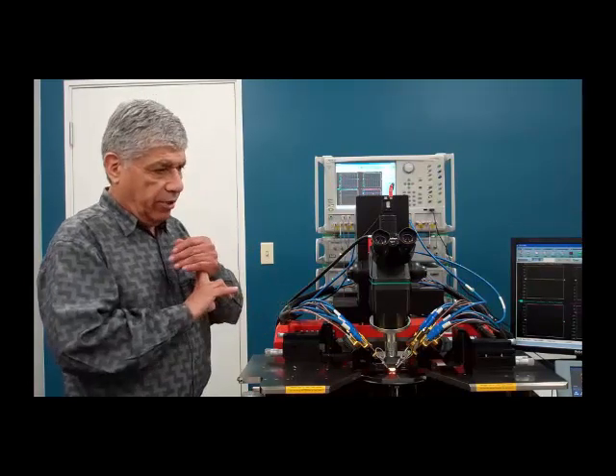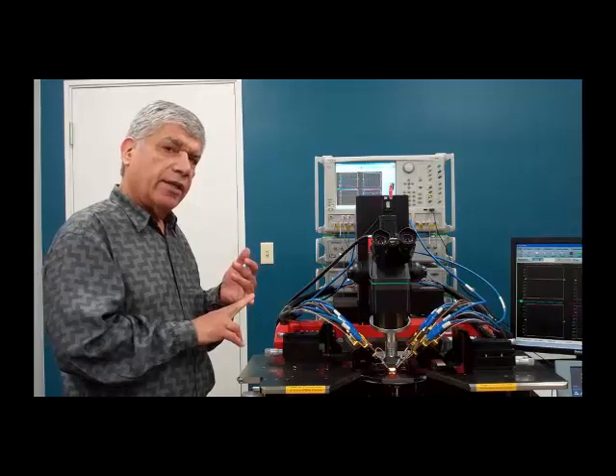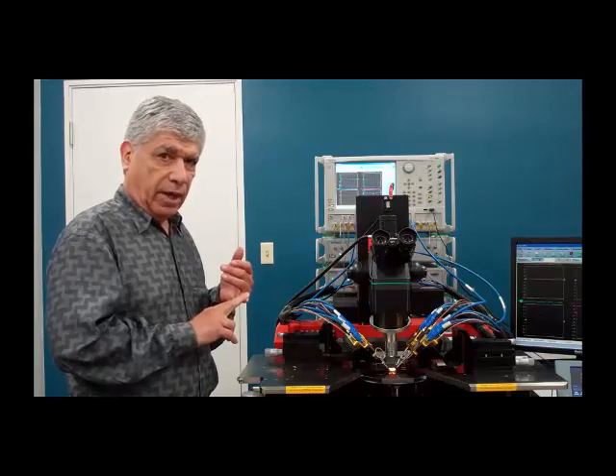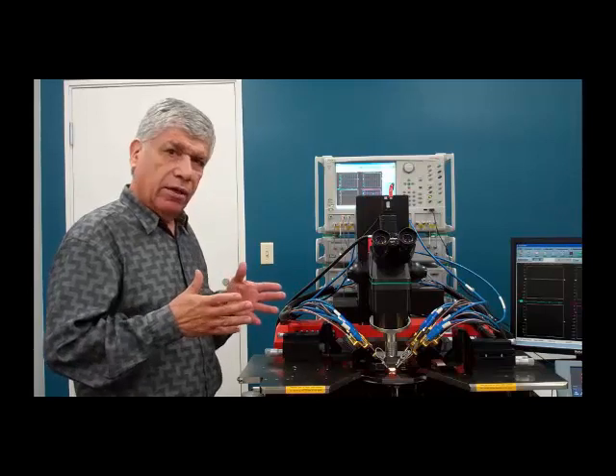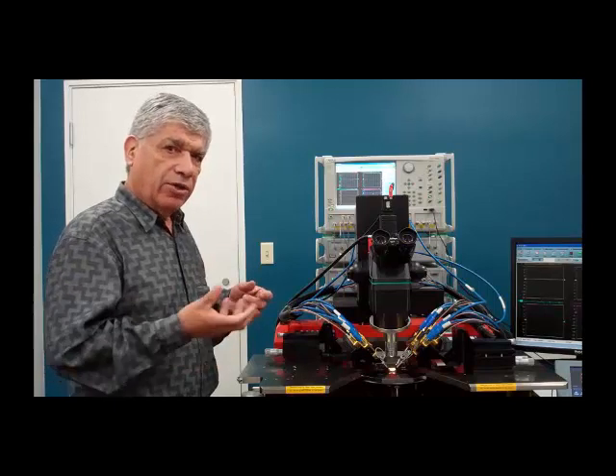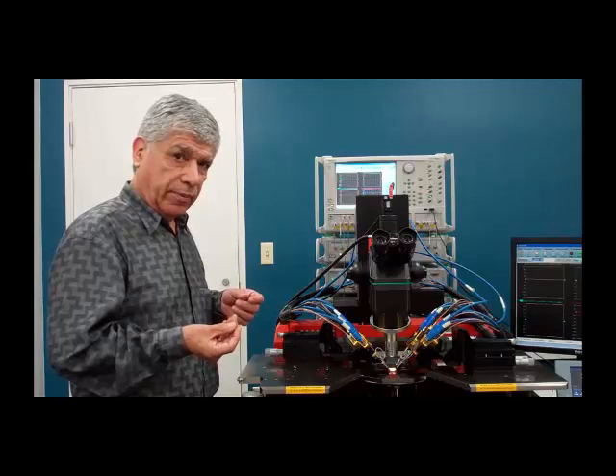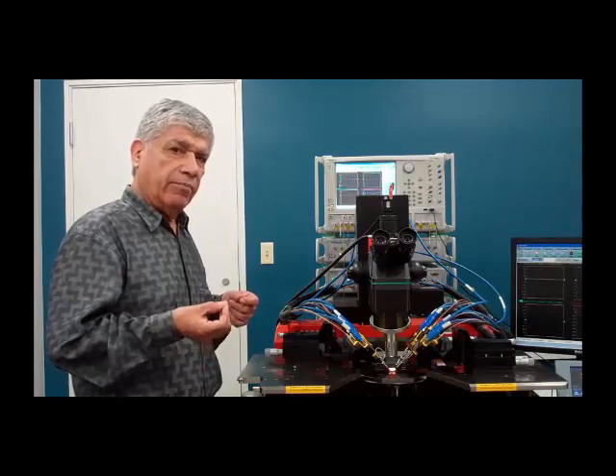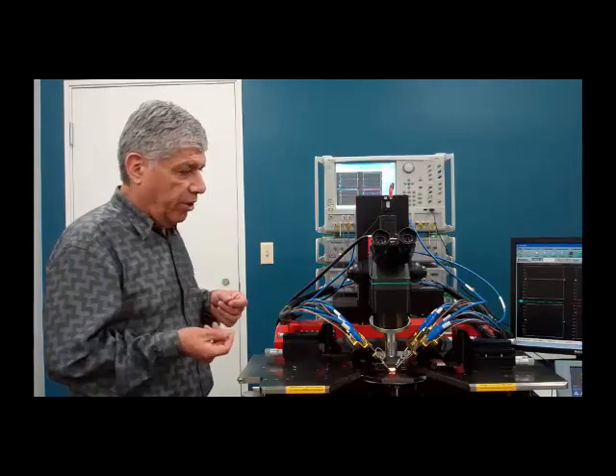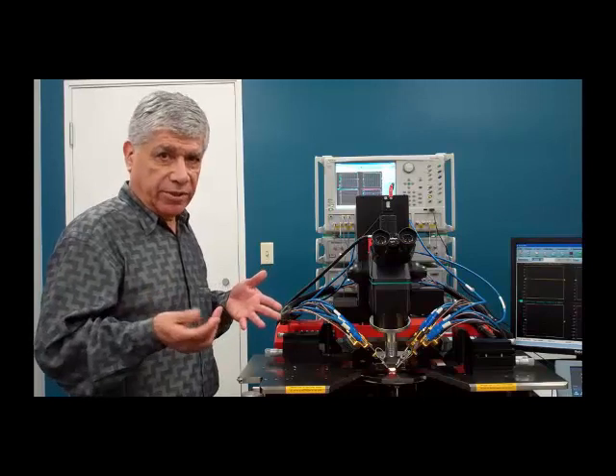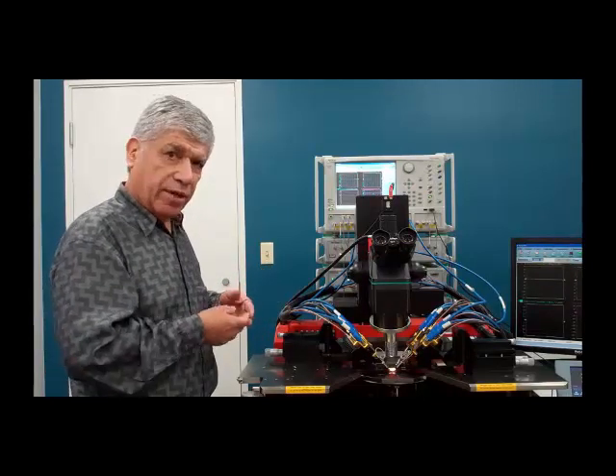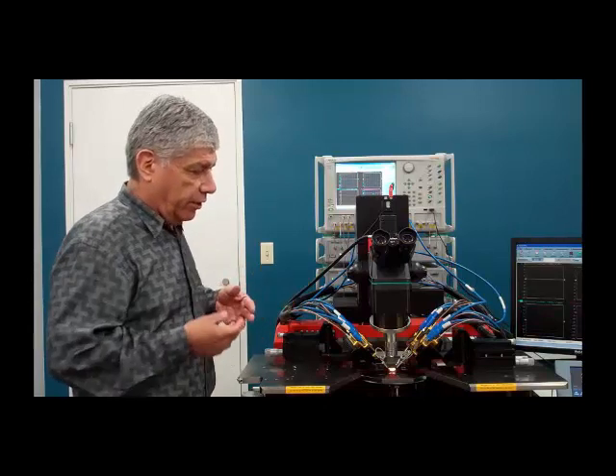So getting back to the 110 versus 145: 110 is covered with a 1 millimeter connector. And the 1 millimeter connector can go up to maybe 130, let's say, gigahertz. If you wanted to go to higher frequencies, up to 145, you need a smaller geometry connector, which is why Anritsu developed the 0.8 millimeter connector. With the 0.8 millimeter connector, we can go up to basically above 150, up to 160 gigahertz or so. So the modules are then performing up to 150 with the 0.8 connector.